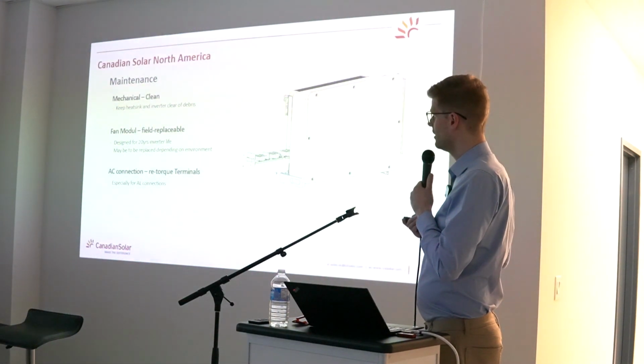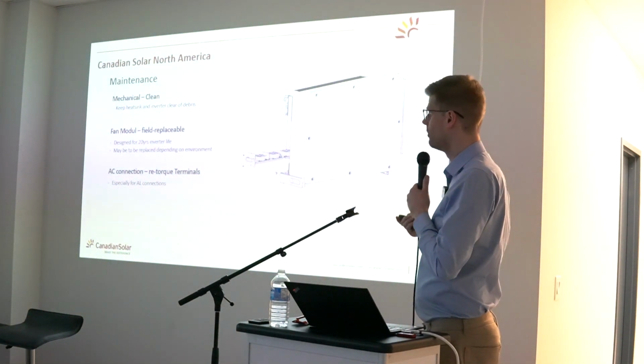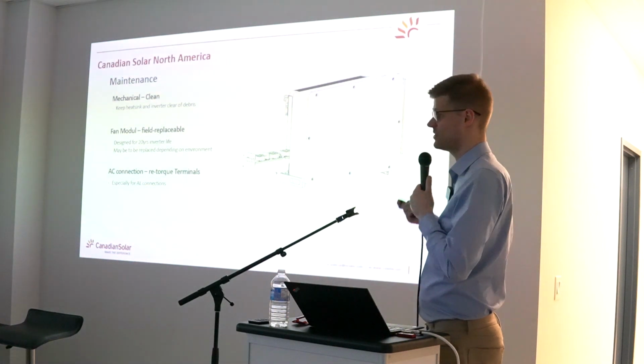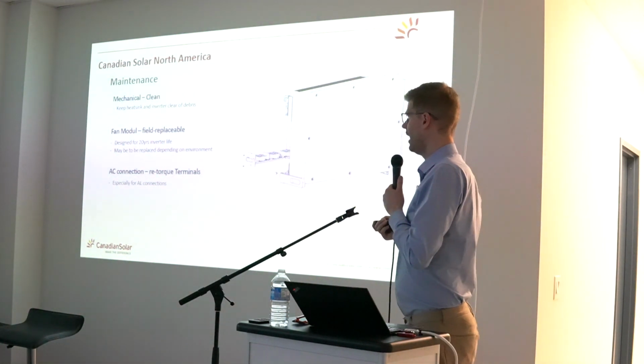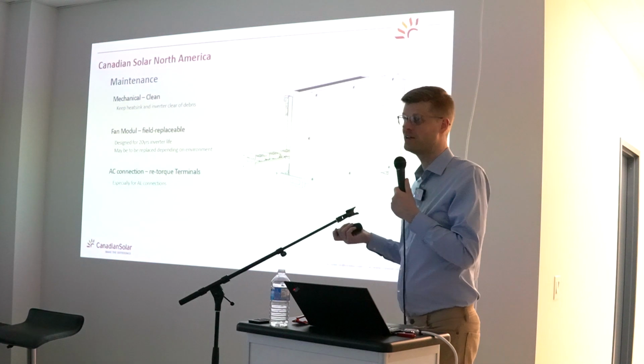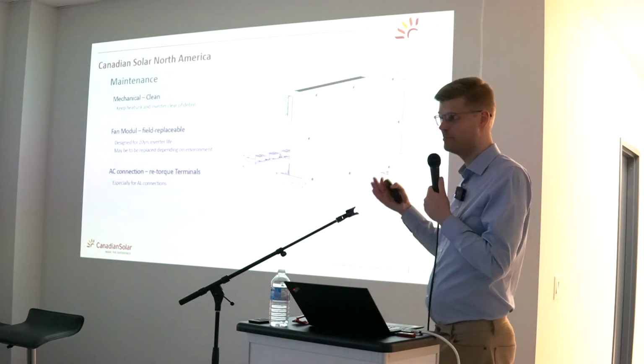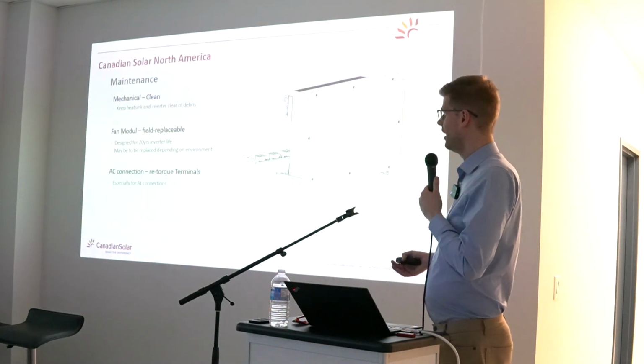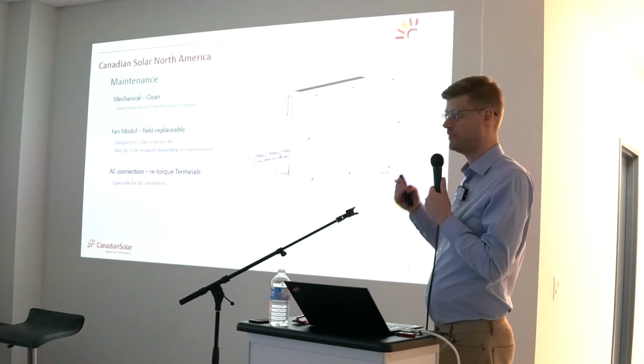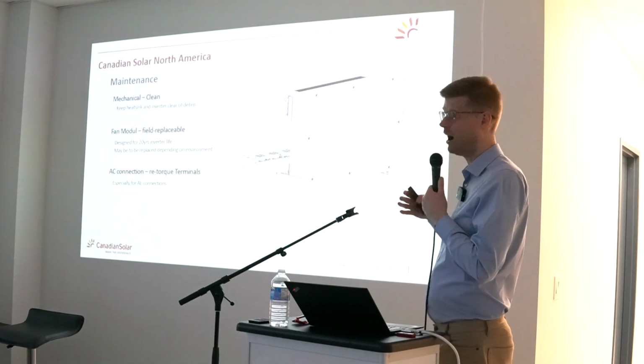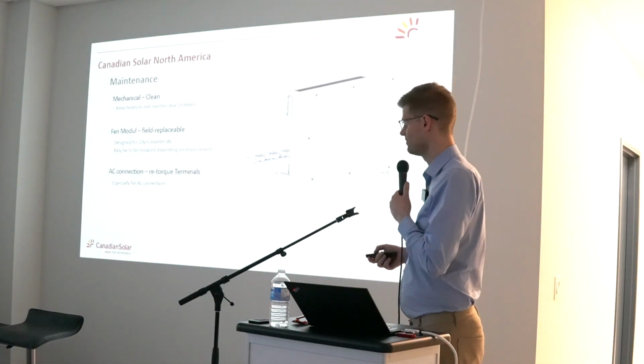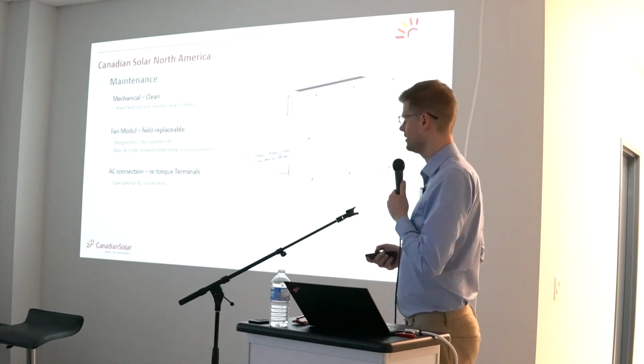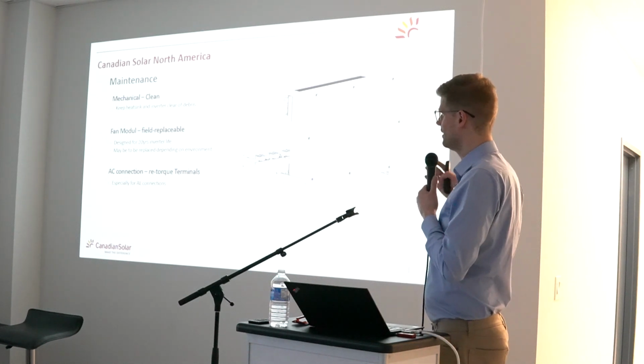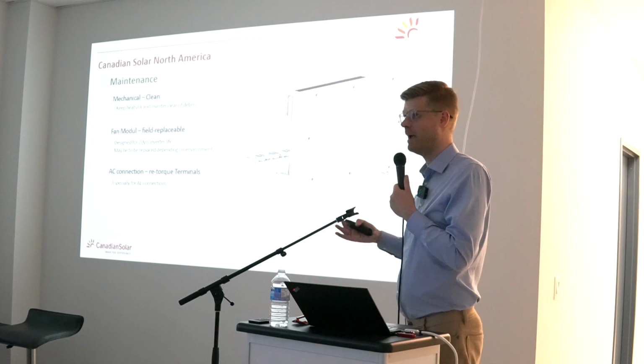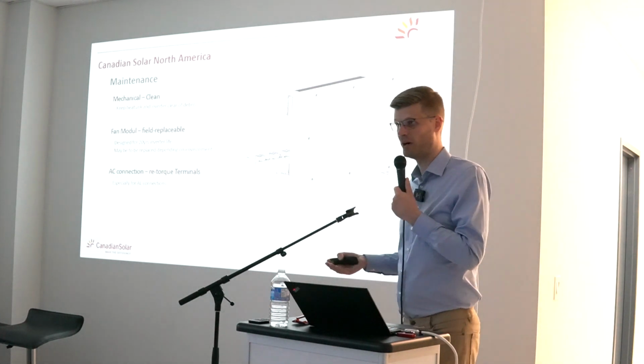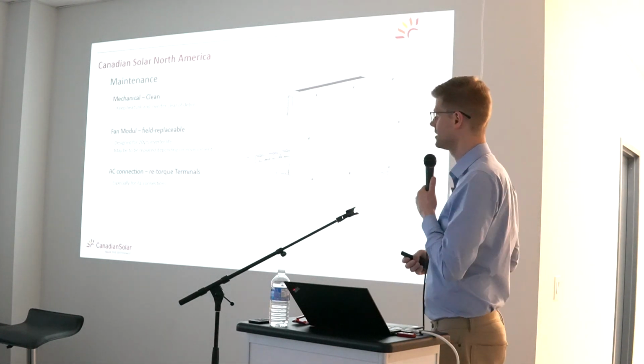What we generally recommend is that for AC connections, specifically with aluminum, that you retorque the terminals at least after 1 year, probably earlier, just to make sure that you have a very, very good connection at these high current setups. Even on smaller units, this is a good idea to do. But other than that, the inverter is basically maintenance-free. There are no user-serviceable parts besides the fans I mentioned.